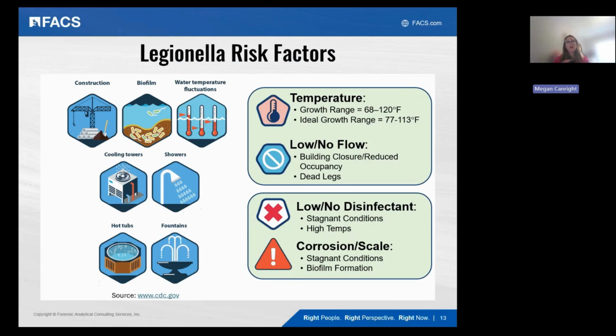Regarding Legionella risk factors, we often look to Legionella as an organism whereas if we control for it, we're typically controlling for other organisms too, since it has a fairly wide growth range. It's not always the case that controlling Legionella controls all organisms, but it's often used that way. The ideal growth range for Legionella is between 77 and 113 degrees according to the CDC, but it can grow at a wider range, between 68 and 120, and sometimes even outside that.